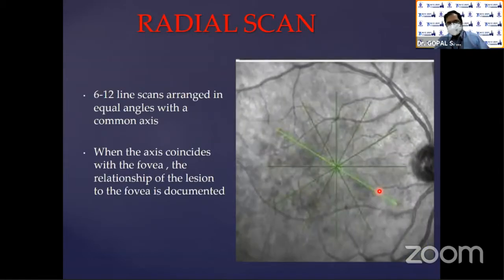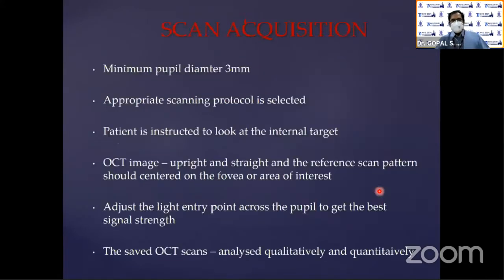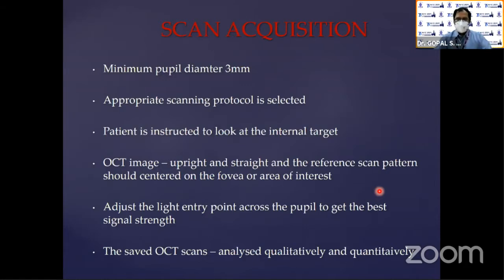You can also have radial scans, which are more for screening, and a 3D scan — either six by six or seven by seven — and in new machines it can go up to 12 by 12. For scan acquisition, you should have a reasonable pupil diameter of approximately three millimeters or more. The appropriate scanning protocol is selected and the patient is instructed to look at the internal target.